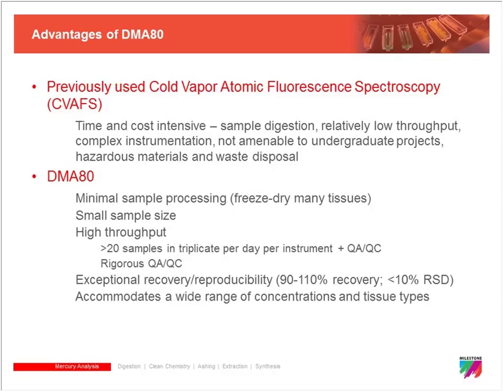We get very high throughput with the DMA-80. Conservatively, I'd say it's very feasible to get over 20 samples in triplicate run per day per instrument, including on top of that a number of QA/QC samples. Our lab is quite rigorous about QA/QC, so with every run we have at least one liquid standard and one certified reference material. Very often we have more than that. If we're looking at a wide range of concentrations, we might use more reference materials that span a wider range. And about every 20 measurements, we will also rerun a liquid standard. That's a lot of extra samples for QA/QC, but because the throughput of the machine is so high, it really isn't an issue. We can still put through a lot of samples.